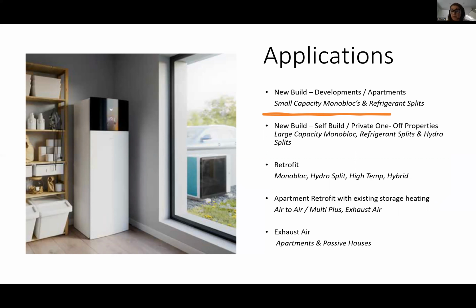For retrofit, the monoblock will be really useful because you don't have any indoor unit with it. So there's less disruption in using a monoblock. The hydro splits, as I said earlier, are a medium temperature, so they will run up to 60 degrees in heating. And the high temperature units, where you have maybe an older period house with very nice old cast iron radiators or something like that, where the radiators can't be changed and therefore you want to keep the system as a high temperature system, that's where it works really, really well.